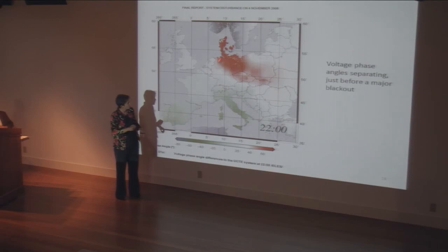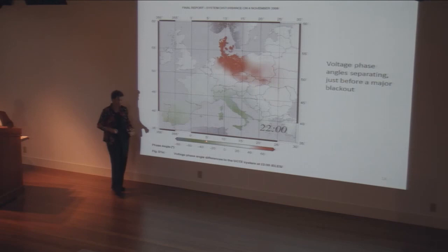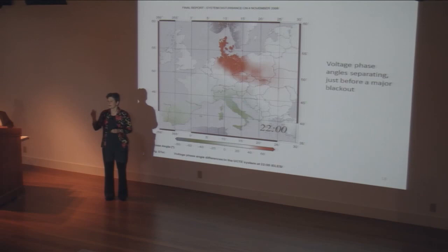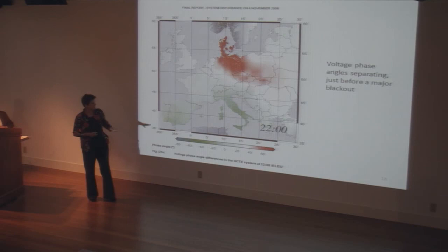They had lost a couple of transmission links, so there was a big impedance between north and south. As a result, the angles pulled apart by tens of degrees to where the system would have become completely unstable had there not been relays that opened and said, this is too far, we're separating. Essentially, the European grid separated into different chunks, and some load was lost. This was not a good day.